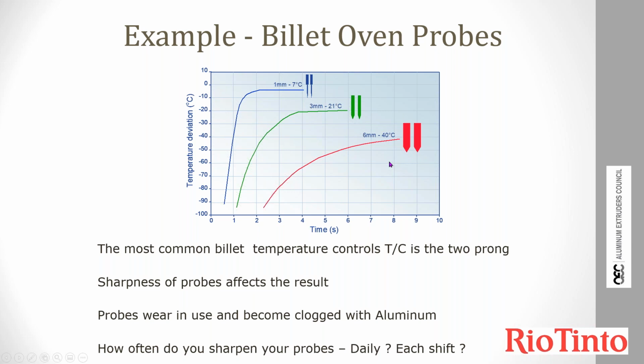This was one particular set of circumstances - don't take these numbers as what it would be like in your billet oven. But the point is, as long as your probes are sharp, smooth, and everything else is lined up correctly, as Danny says, they'll give you a good reading. There'll be an offset, but that's easy - the oven manufacturer will build that offset into their control system.